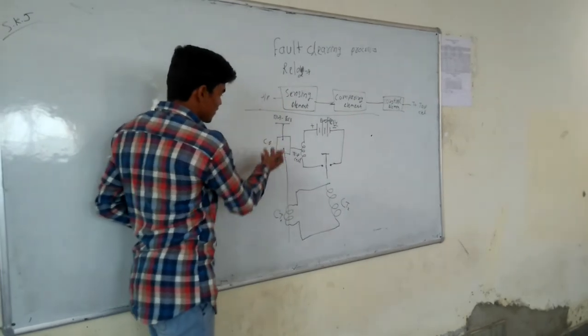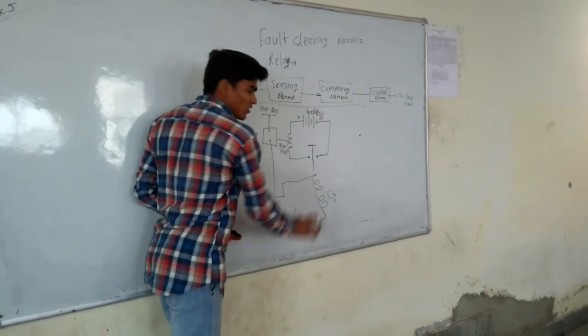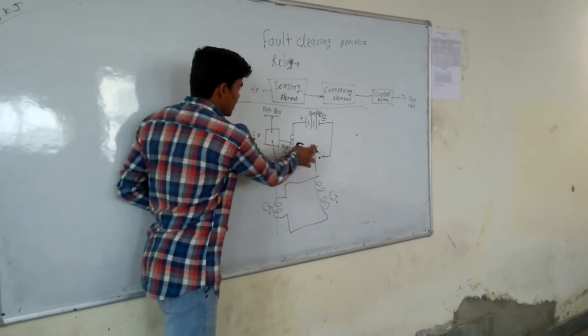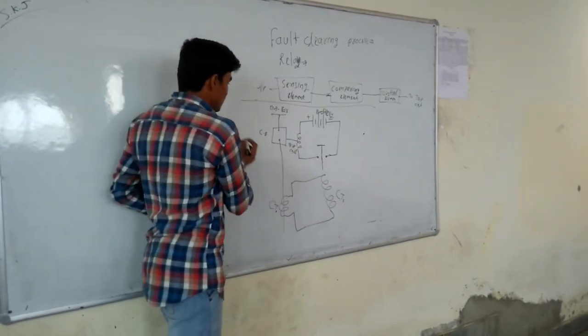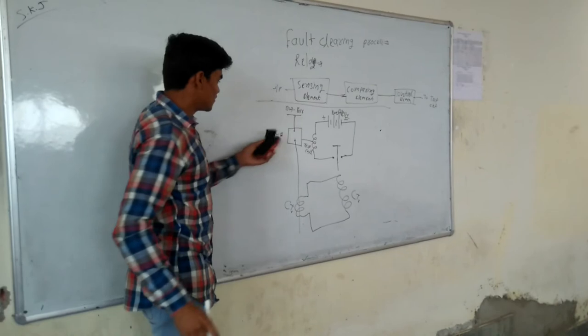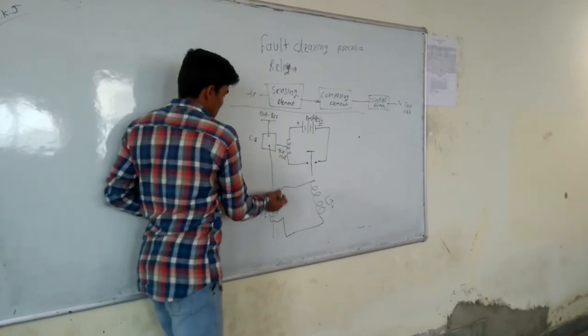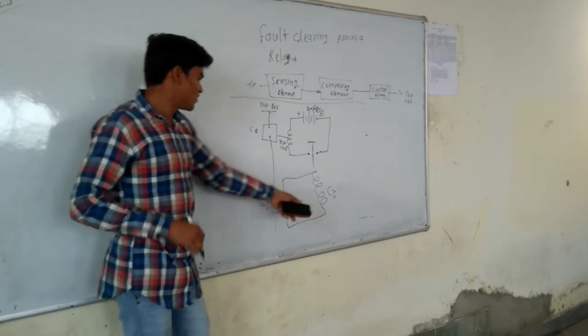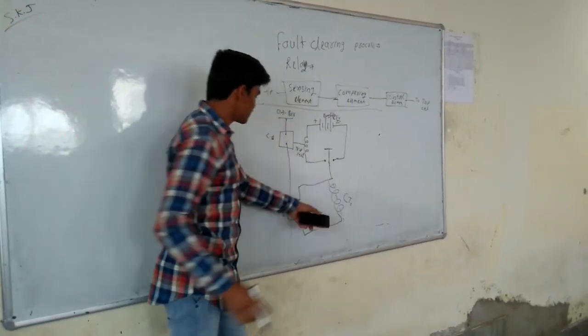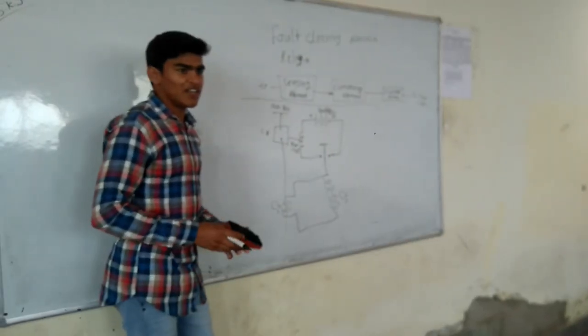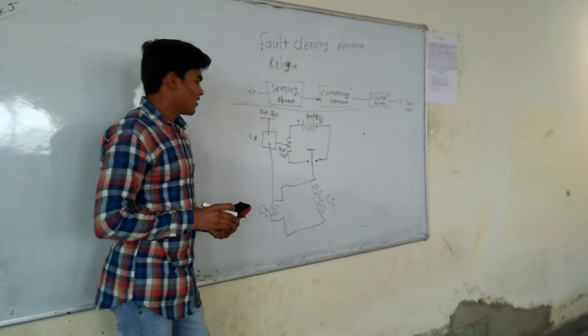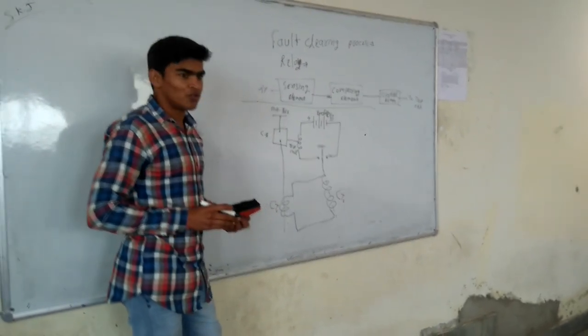In normal conditions, there is no current to the secondary of the current transformer and relay not operated. When you have any fault in this circuit, the excessive current here leads to the secondary of the current transformer. The excessive current is sensed by the relay. The relay sends the command to the breaker to open its contact.